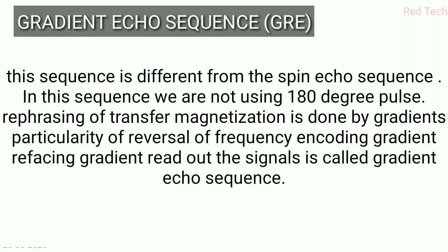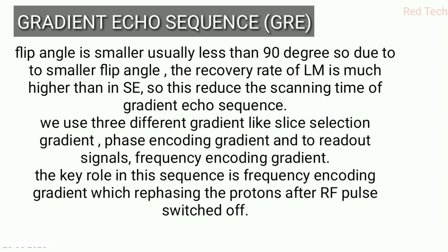In this sequence, we are not using any 180-degree RF pulse to rephase the transverse magnetization. This is done by the gradient — particularly by reversing the frequency encoding gradient. Refocusing and reading out the signals is called the Gradient Echo sequence. No 180-degree RF pulse is used; instead, slice selection, phase encoding, and signal readout are all done by the gradient coils.